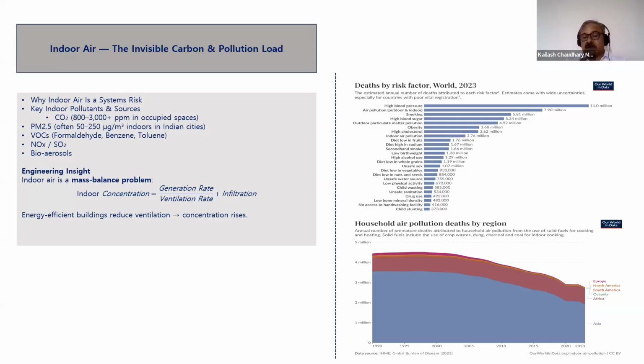The concentration of these contaminants will depend upon 3-4 factors. One is generation rate, the rate at which it is being generated. Another is ventilation rate, the air change per hour, as we call it in the office. Then filtration efficiency and outdoor pollutant level, because the air coming from outside will have the pollutants. So it depends upon all these.